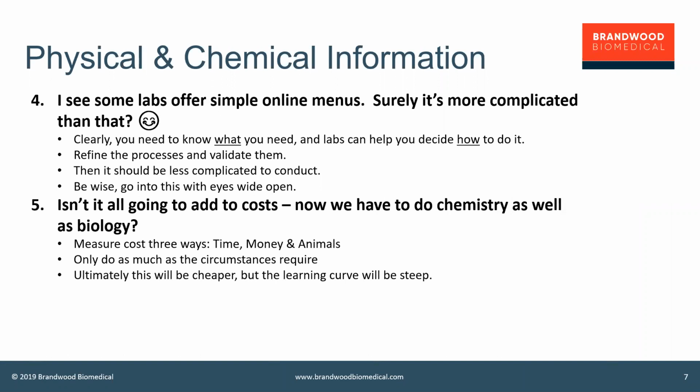Ultimately, it's going to be cheaper, but there will be a steep learning curve, I think. There shouldn't be, but I'm afraid that there will be quite a steep curve. And chemistry can be done more quickly. It's these days more sensitive in terms of finding out what's in there, and then you can go to the literature and the toxicology of what's present. But learning to do that properly is going to take some time and some adjustment, I think. Yeah, that's true. And also, there are a number of biological endpoints that won't be able to be addressed using the chemical and physical characterization information. You will still have to perform some biological tests. I'm fairly certain of it.